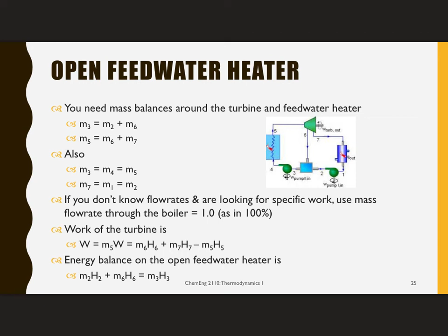This is a diagram of a closed feed water heater. So what you see here again is the material comes out of the boiler, goes into the high pressure turbine. It then leaves that turbine, but there is a split. Some of it's going to go on to the low pressure portion of the turbine and the condenser and the pump 1. Some of it is going to go into the closed feed water heater.